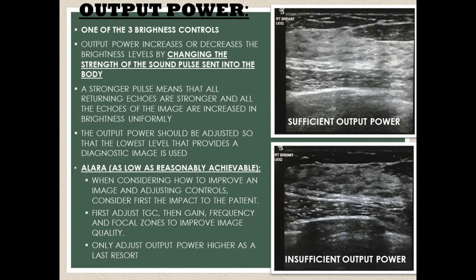The output power should be adjusted so that the lowest level that provides a diagnostic image is used. And we always want to consider the ultrasound safety principle, ALARA — as low as reasonably achievable.